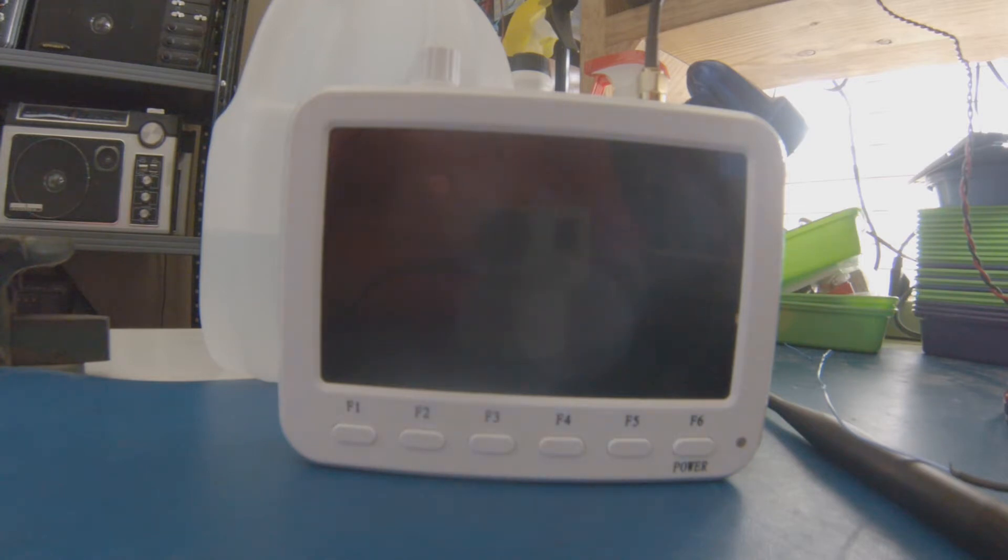What you get in the box is this white box. It has six soft keys across the bottom, a scroll wheel on top, and the antenna connection on top. It doesn't give you any warning about input levels, but with any spectrum analyzer I would recommend no more than minus 30 dBm and no DC at all.